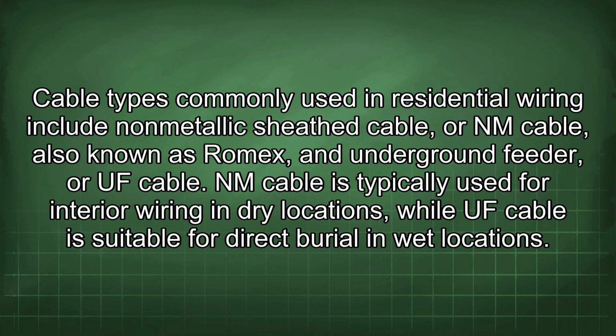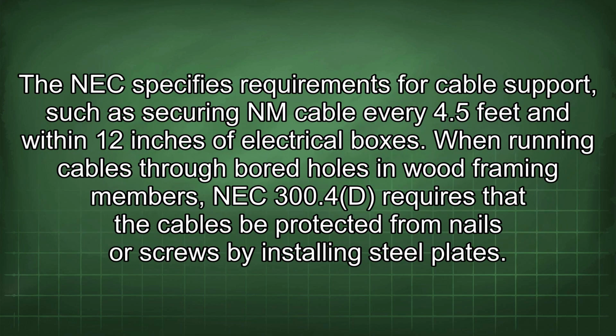NM cable is typically used for interior wiring in dry locations, while UF cable is suitable for direct burial in wet locations. The NEC specifies requirements for cable support, such as securing NM cable every 4.5 feet and within 12 inches of electrical boxes. When running cables through bored holes in wood framing members, NEC 300.4(D) requires that the cables be protected from nails or screws by installing steel plates.